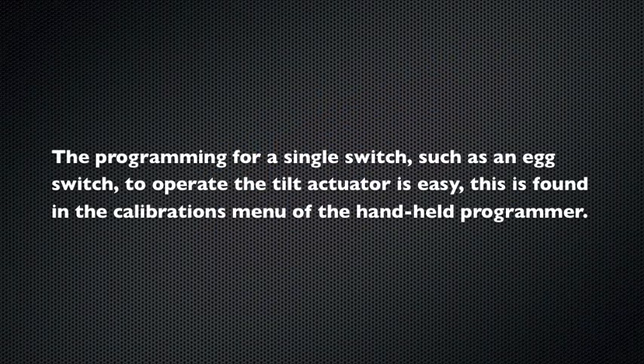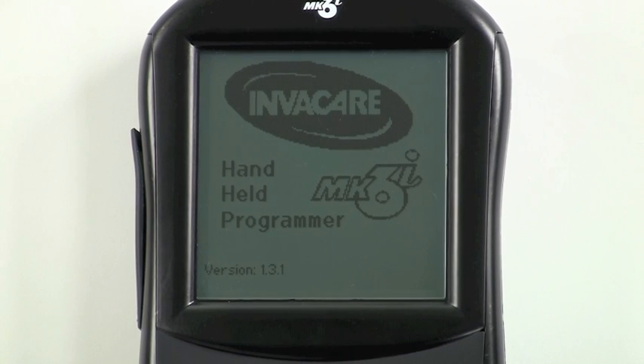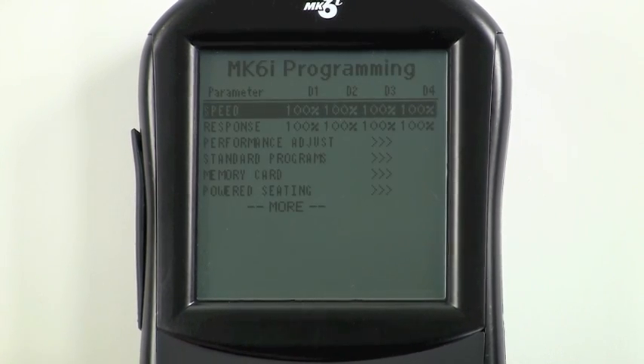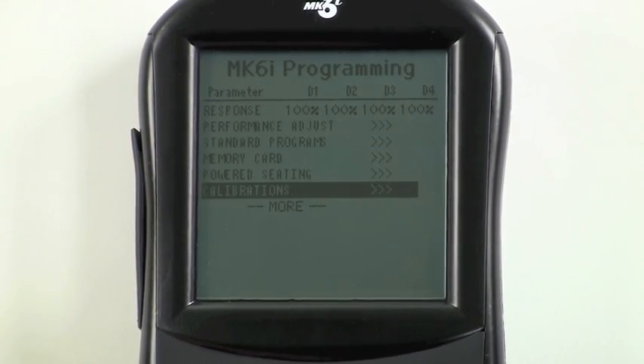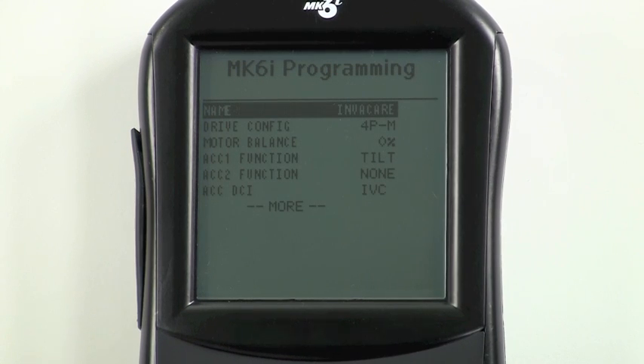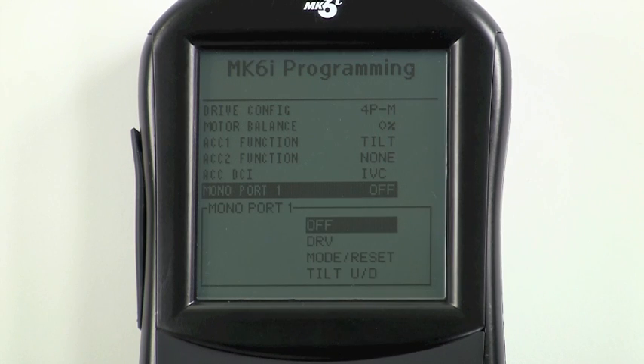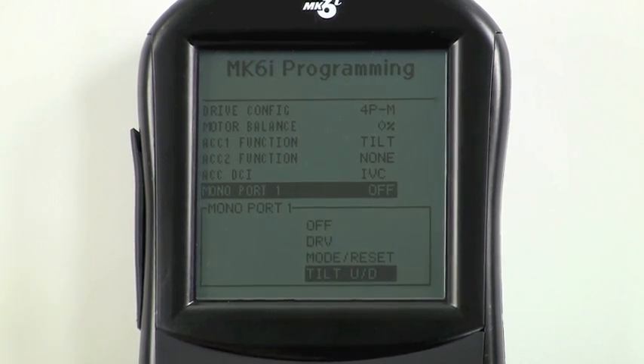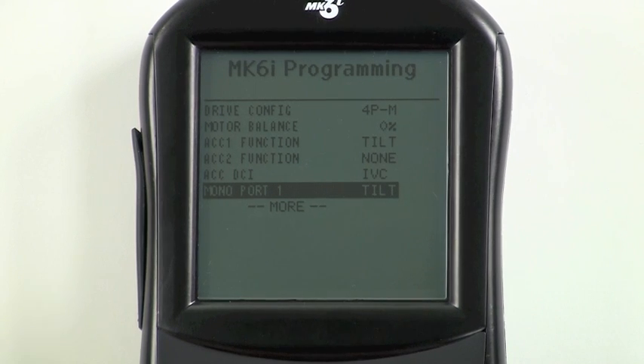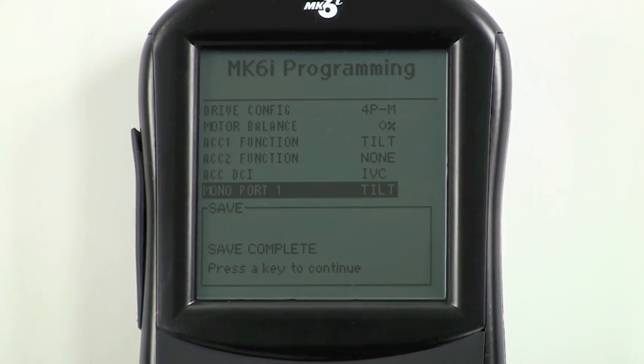The programming for a single switch such as an egg switch to operate the tilt actuator is easy. This is found in the calibrations menu of the handheld programmer. First, turn the programmer on, scroll down to calibrations, and press select. Scroll down to monoport one and press select again. Choose tilt up/down, press select, press save, press save again, and you're done.